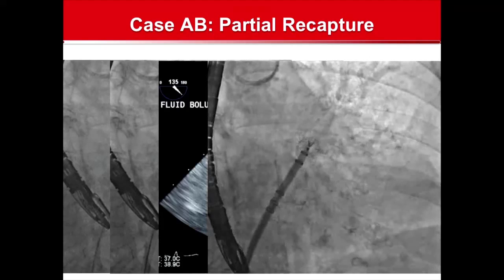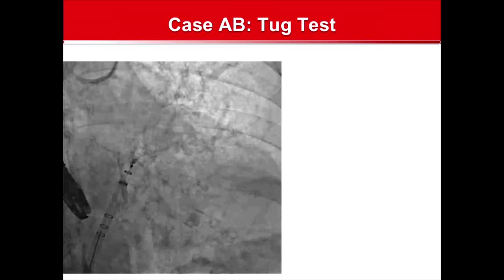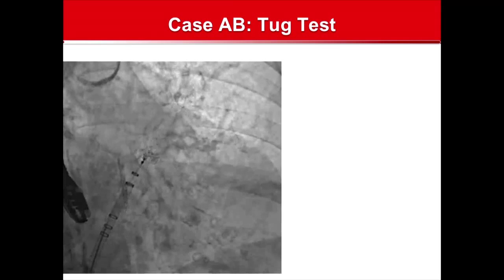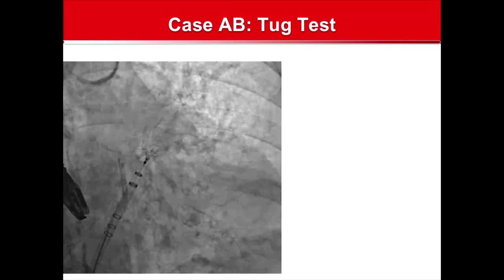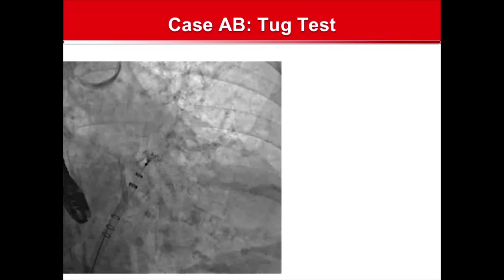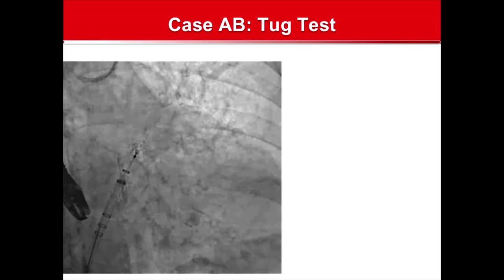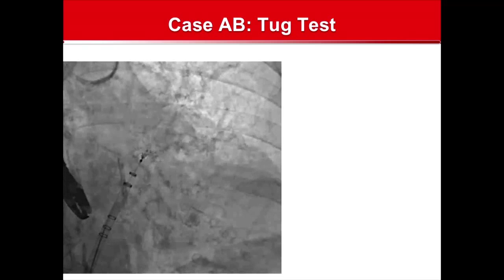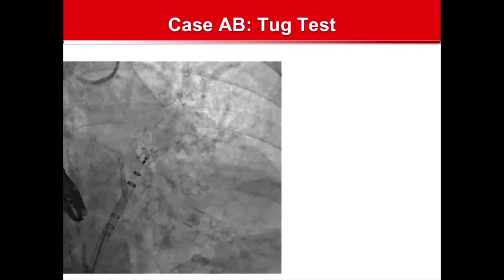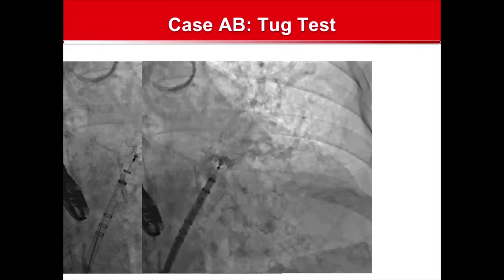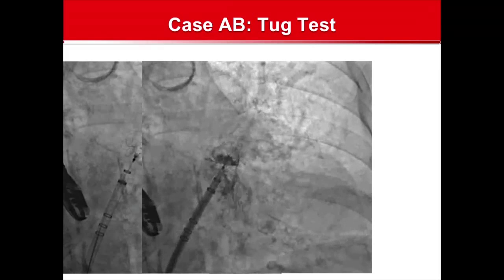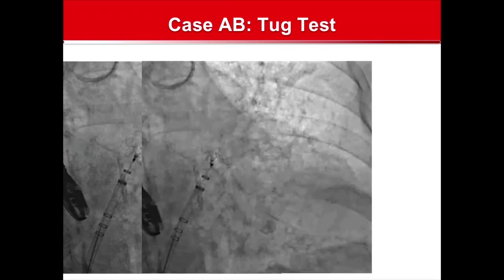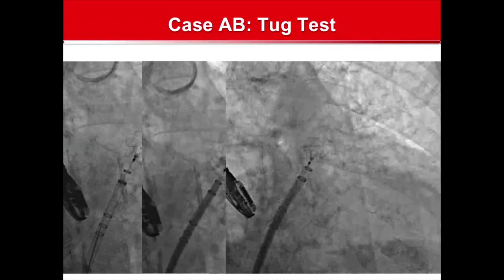Following that partial recapture, we took a cine angiogram again to check the position, and we also want to check the stability of the device, and to do so, a Tug Test is typically performed, and sometimes we do 2 or 3 Tug Tests to make sure that the device is safe. And here what you're seeing is a movement back by pulling the cable and letting the device bounce back into position, and you can see that this device is very safe. It's entrenched in the left atrial appendage. And we observe this motion both on cine angiogram as well as on TEE, and we then perform another injection again here to see that the device has not moved in position.